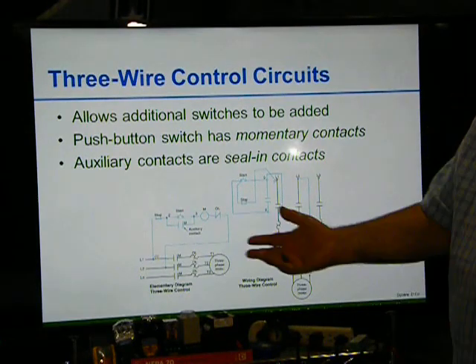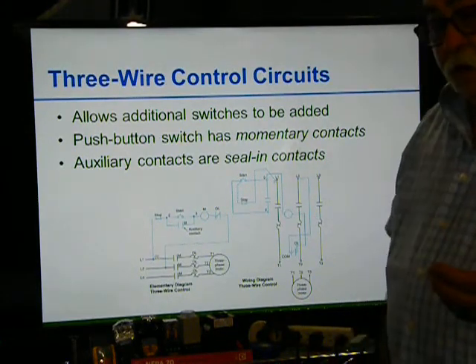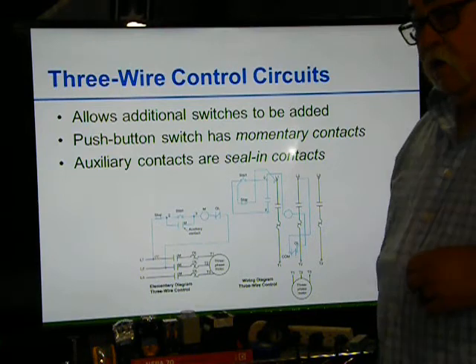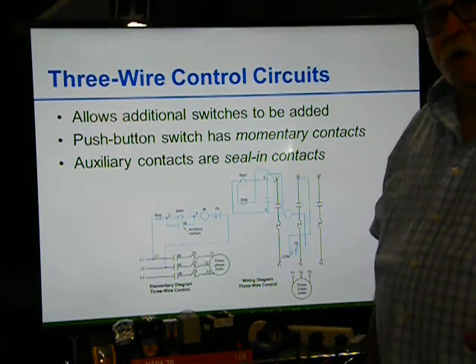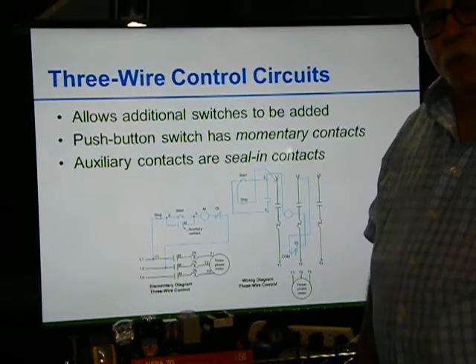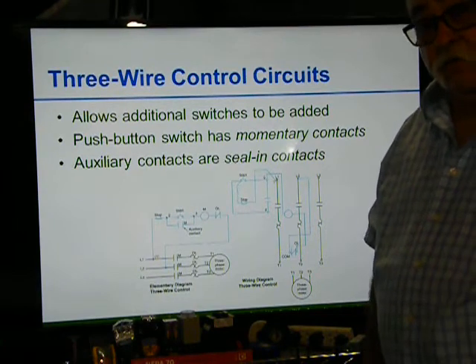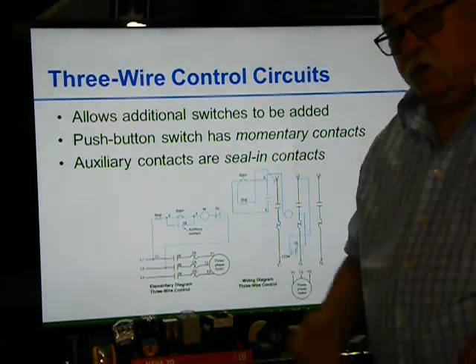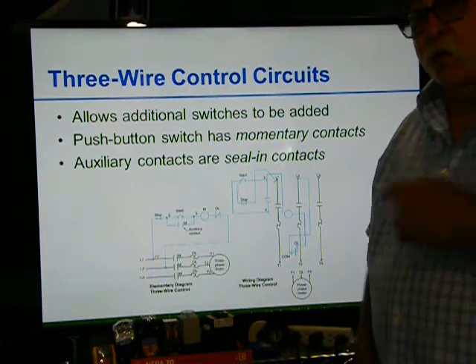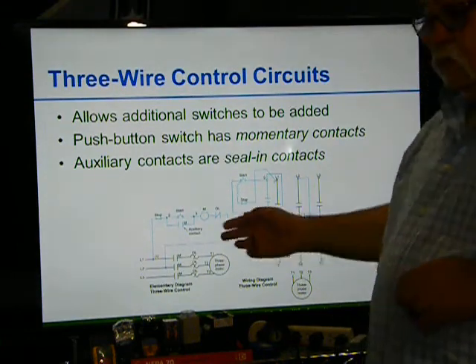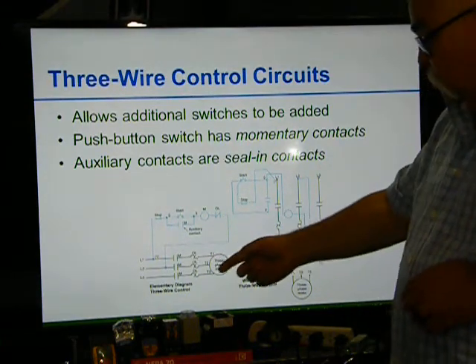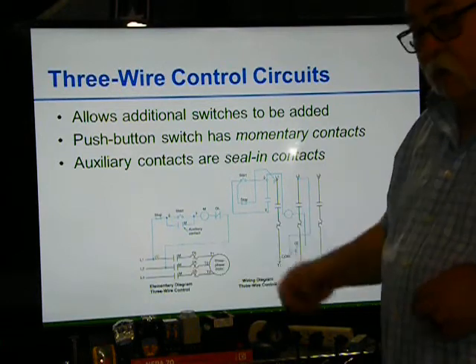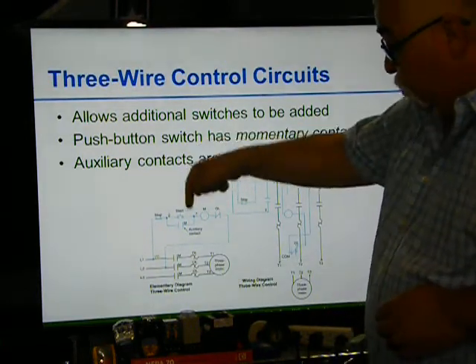The advantage of this over a two-wire: you leave the switch on, power goes off, power comes back on, guess what? The motor's coming back on. Or you're working on the motor and you forget to turn the switch off, and you walk over to turn that breaker, guess what? That motor's going to come on right away. With a two-wire, the only way, on the three-wire, the only way this motor is going to turn back on, the only way this contactor is going to close is you go over there and you hit the start button.